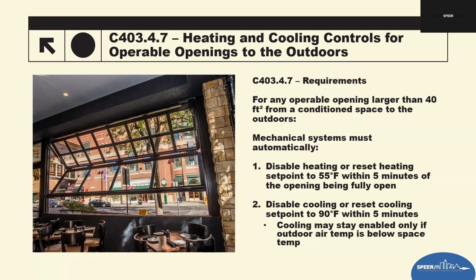So these controls are meant to prevent simultaneously mechanically cooling or heating when you've got uncontrolled outside air coming in. This happens a lot with sports bars, like retail spaces, but now we're also looking into their loading docks, things like that. When doors open up, those warehouses, if they're being conditioned, must also be tied in. So there are very important exceptions here, though. There are things that are meant for situations where the requirement is either impractical or unnecessary. And I'm going to pause with that, saying that there's a lot of people that may start using that language to get away from this.